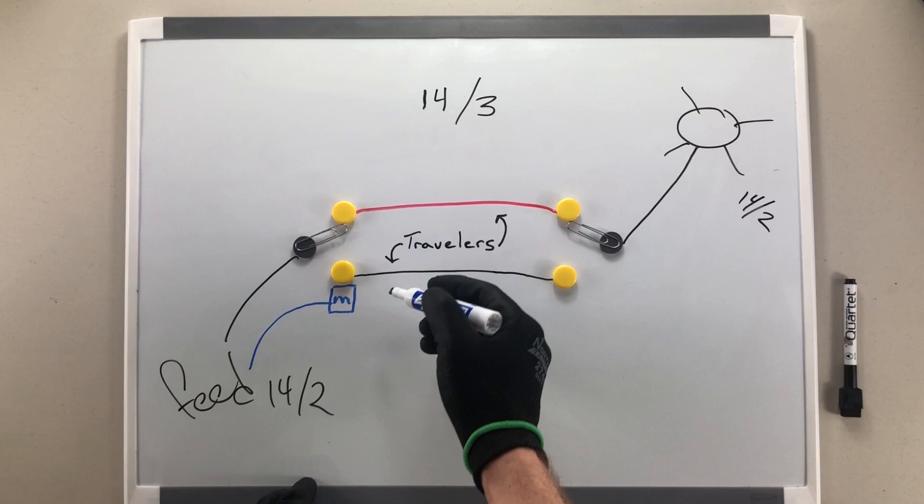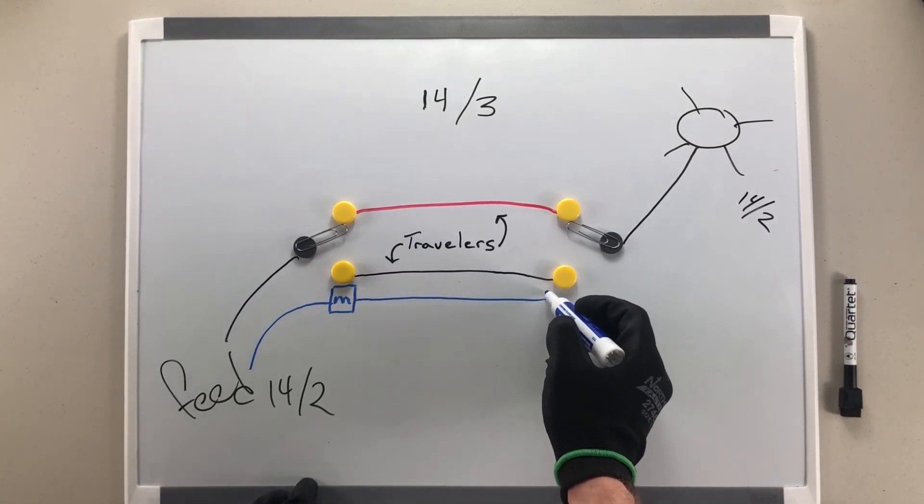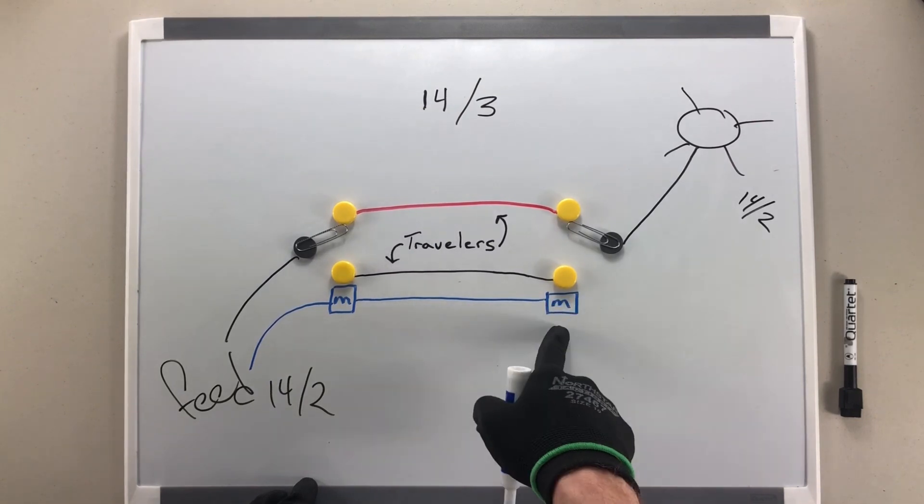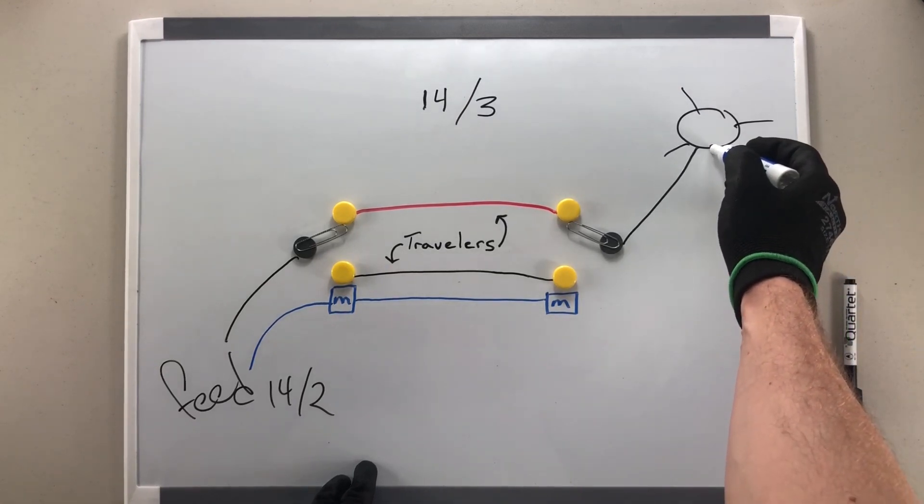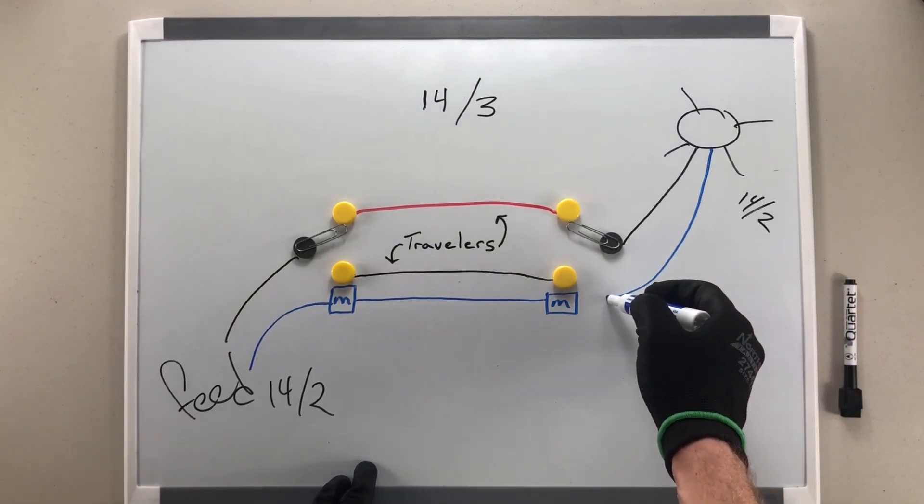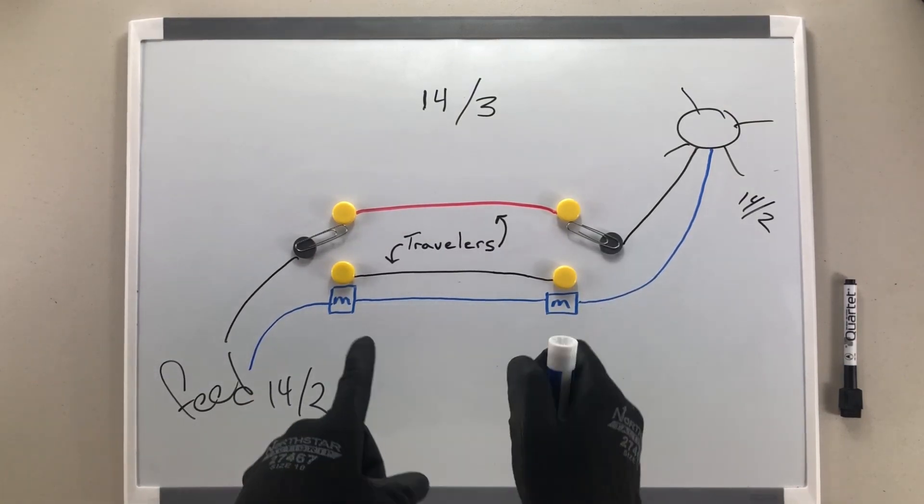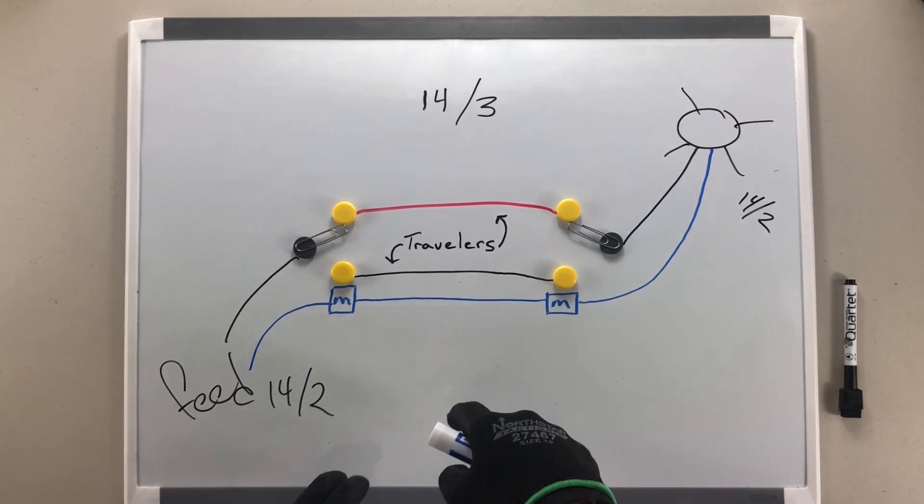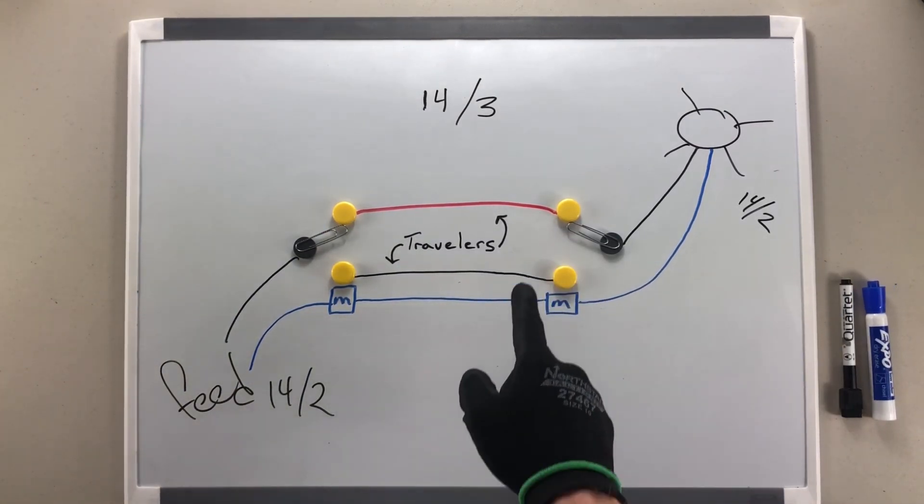We also have a neutral in our 14-3, so that will come across between our two 1104 boxes, and we'll make another wire nut connection here with our neutral. We also have a neutral in our 14-2 from our light, so that will come down and connect as well in the box with our three-way switch. None of our neutrals ever get connected to any of the switch terminals. Those are only for the current carrying conductors that we label as hot wires, like the red and the black.